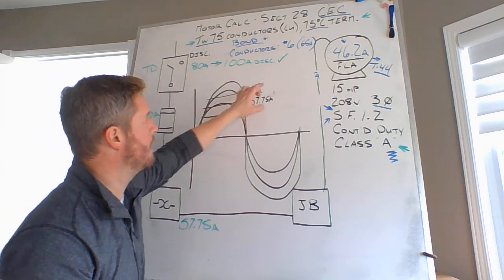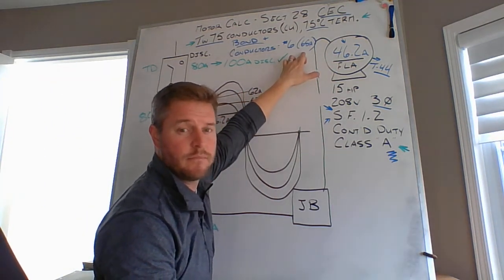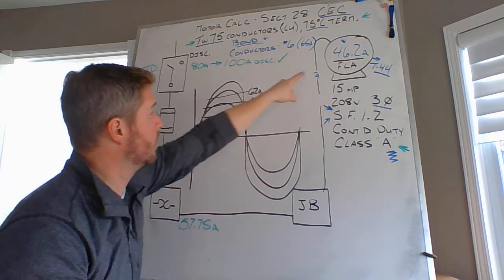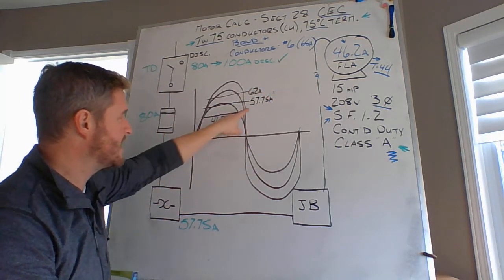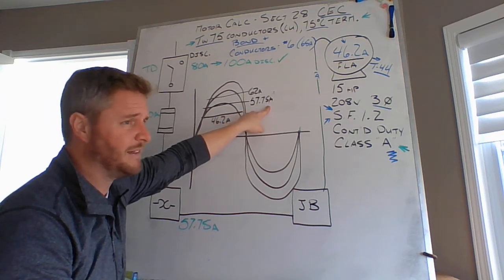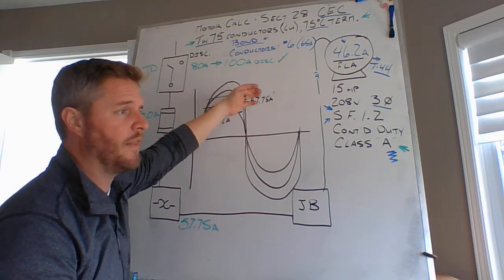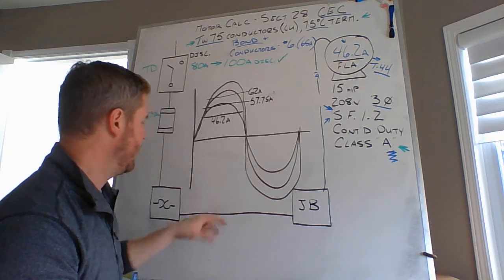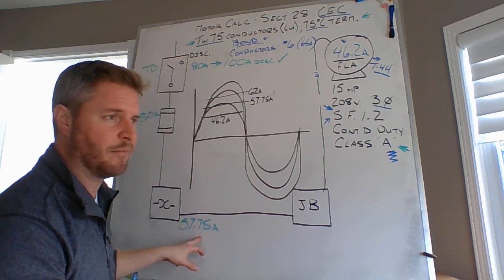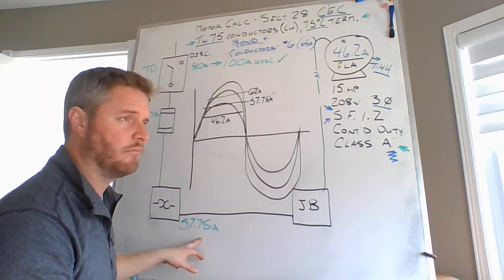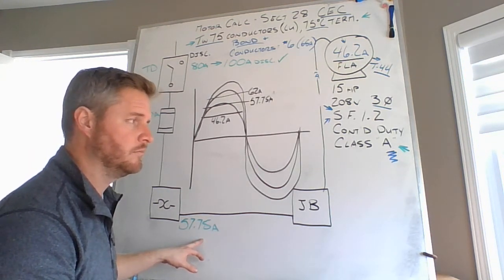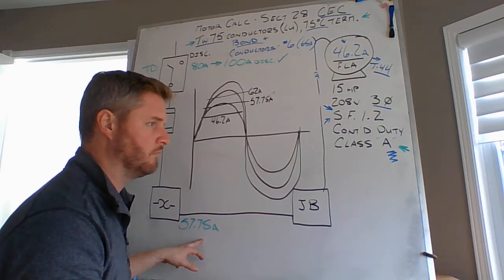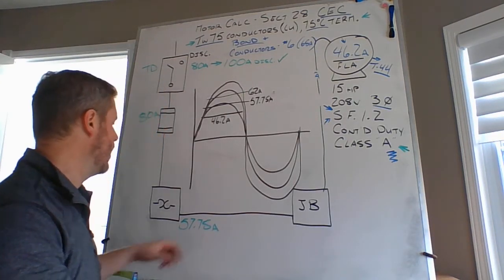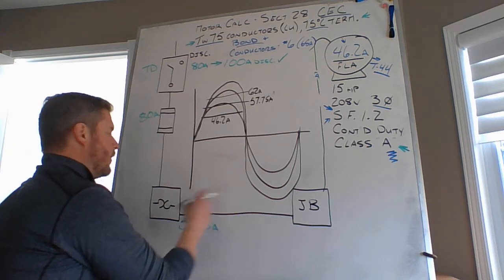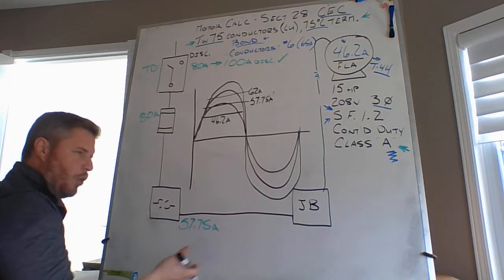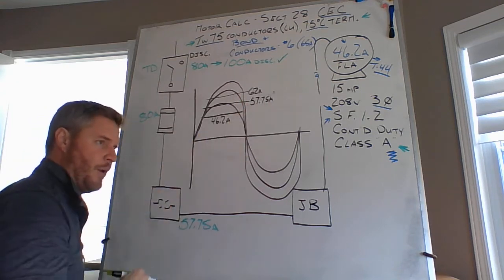But we only got the 62 amps, and my conductors are good for 65. So there you go. Your overloads are protecting your conductors. Totally. They saw the 57.75 amps, and they were like, yeah, all right. But then you went above and beyond that, and you pushed that motor to do more, and the overloads were like, nah, that's not going to happen. No, we're not doing that today. Just calm it down, bro. It's Wednesday. Really not a big deal. You don't have to get this job done in one day. Calm down. Okay? So at 62 amps, the overloads open. That opens your control circuit, effectively shutting down the motor.